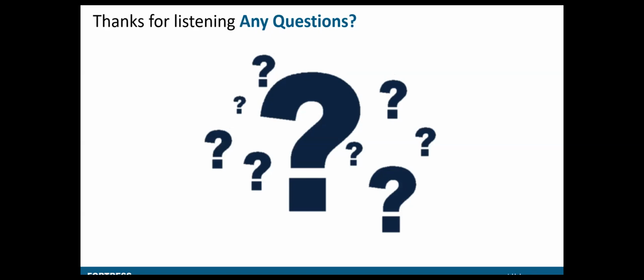Excellent, thank you. I think this question was made for me. I've answered it on quite a few occasions over in Europe recently. How can a single tongue meet PLE, which relates to Eve's last slide, where we were showing just a single interlock in a performance level E application? We use fault exclusion primarily on the metal components, the tongue itself. So you could literally hang a car off one of our tongues.